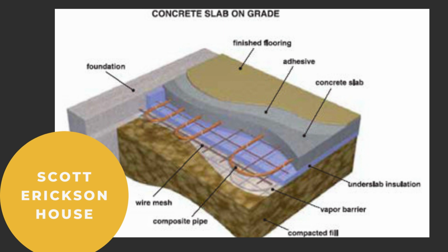We had 3 or 4 rooms in it wet, but part of the construction challenge is when they ran the hydronic tubes in the floor, they didn't compartmentalize them by rooms. So had we torn one floor out, it would have affected the rooms that go under the walls and so forth and so on. So basically, we'd have had to tear all the floors in the house out to be able to get the hydronic heating system fixed.